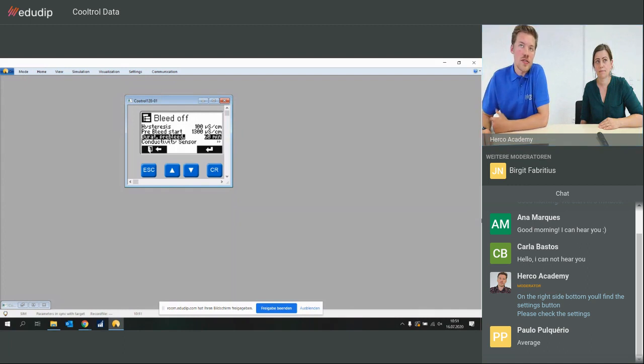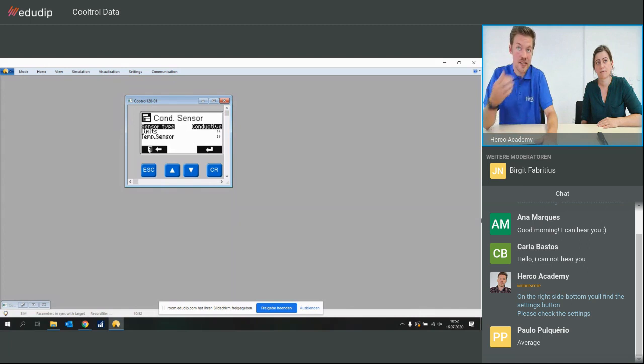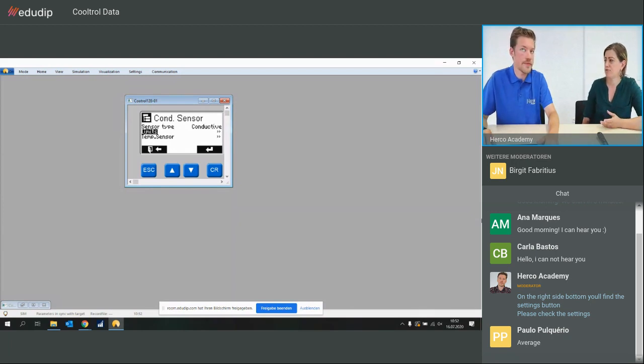And you can also set this up so that you have a minimum duration. So we say, okay, before we go into operation, it doesn't matter how much conductivity we have, we just say, all right, let's bleed off for 10 minutes to be safe during the bleed off process. Then of course we can choose the conductivity sensor, what sensor type it is, conductive or inductive, and also set up limits for it. So basically in the limits, you only have the information if the sensor is broken or there is some kind of short circuit, anything inside that tells us that the sensor is defective. So you set the limits to values that couldn't occur in normal operation. Exactly, right? That's it. Yes.